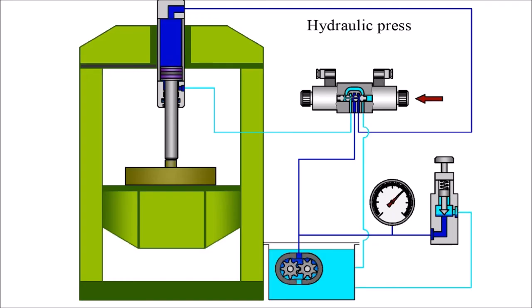So that the hydraulic circuit is protected from excess pressures and hence from overloading, the maximum pressure must be limited. This is achieved using a pressure relief valve. The flow still delivered by the pump flows via the pressure relief valve directly back to the tank. The pressure at this moment is maximum.